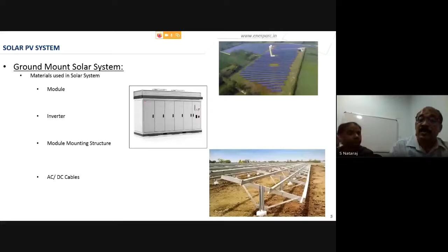Module mounting structure is the major item in the ground mount system. Around 10 years back, it used to be 70 to 80 tons per megawatt. Over time, a lot of value engineering has been done. Now people are using roll-formed sheet metal components, and it has come down to around 25 to 30 tons per megawatt, the current industry standard for steel utilization. Costs have substantially come down too. People are going from 0.9 mm to 2 mm thickness for the structures. This value engineering over 10 years has benefited the industry, making us more competitive globally.